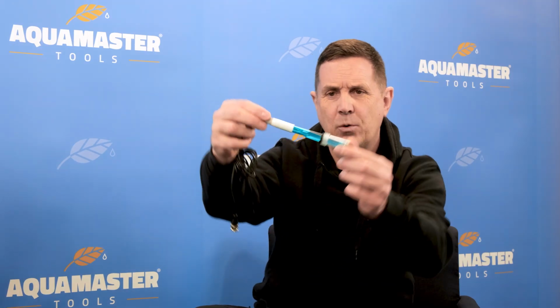The pens have a quite short probe, so that means they have less liquid, and the longer probes contain more liquid, and more liquid means more buffer. That also means a longer lifespan. When we're looking at a normal pH pen, you see the ball in the bottom of a pH pen, that is full of liquid. That's correct. When you get the larger pens, you can actually see the liquid moving around in there a little bit. That means that these will last a lot longer, because they have a lot more liquid, which doesn't basically get contaminated when you're using it over time.